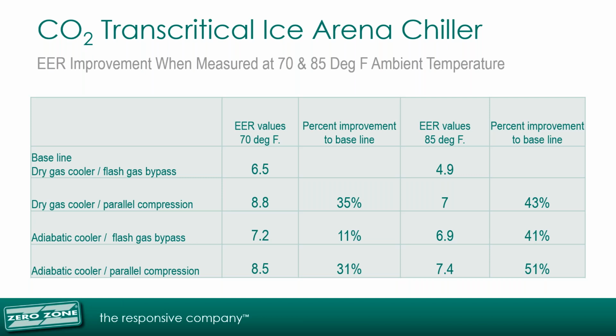We measured larger energy improvements than we originally estimated during the design phase. On warmer days, we have a greater improvement in performance. You get more bang for your buck on hotter days. Dry gas cooler / parallel compression operation was 35% more efficient at 70 degrees ambient and 43% more efficient at 85 degree ambient. Adiabatic cooler operation with flash gas bypass was 11% more efficient at 70 degree ambient and 41% more efficient at 85 degree ambient. When the technologies are combined in adiabatic cooler and parallel compression, it was 31% more efficient at 70 degrees F and 51% more efficient at 85 degrees F, all compared to the baseline.